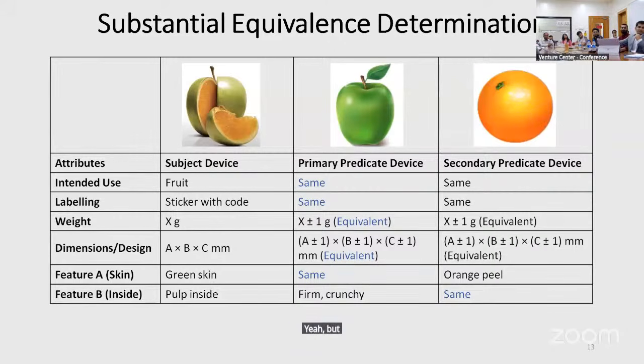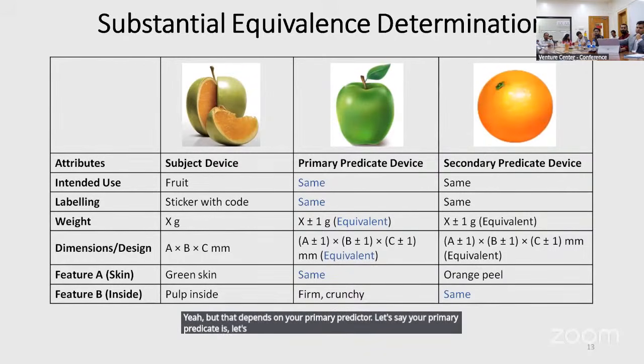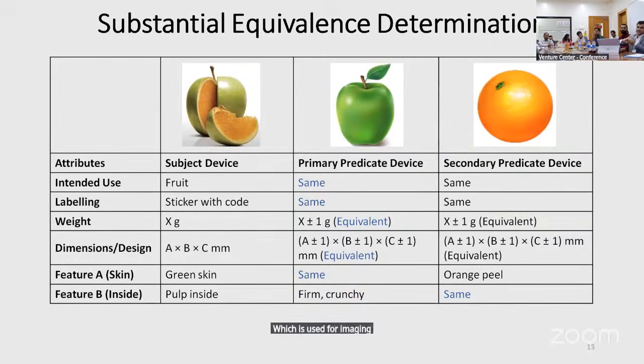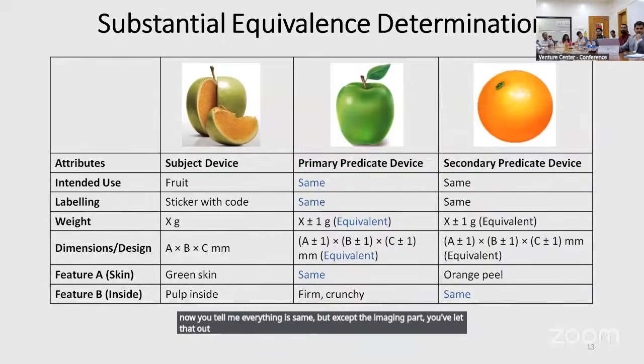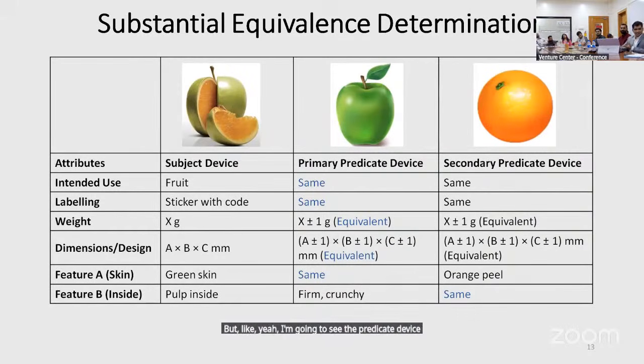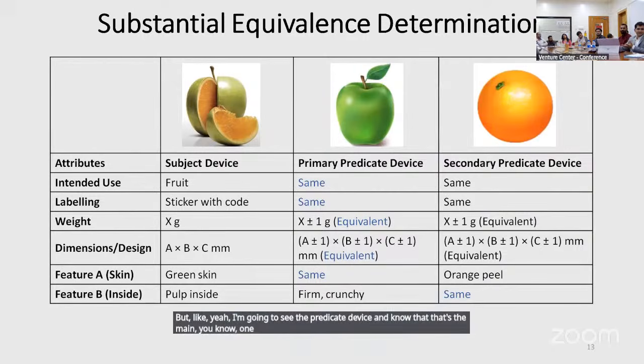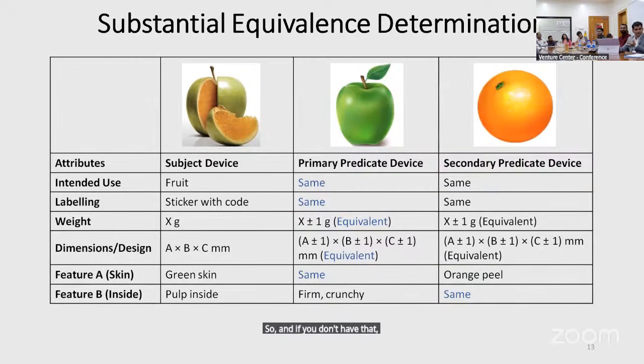Yeah, but that depends on your primary predicate. Let's say your primary predicate is a cystoscope, which is used for imaging. Now you tell me everything is same except the imaging part, you've left that out as a technology characteristic. I'm going to see the predicate device and know that's one of the main technology characteristics it has. So if you don't have that, and you're claiming to be a cystoscope, that's not going to fly.